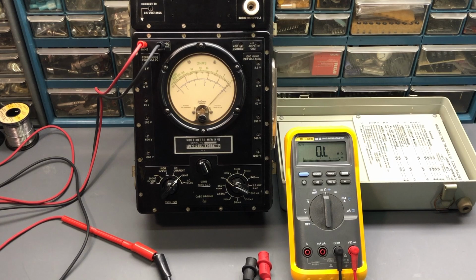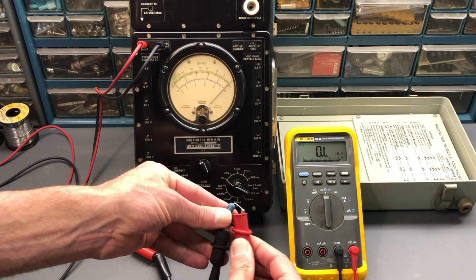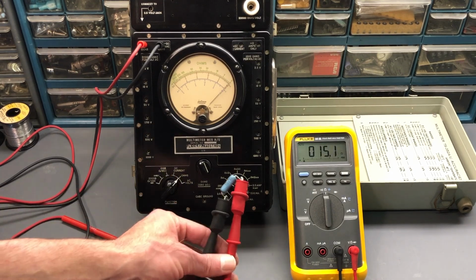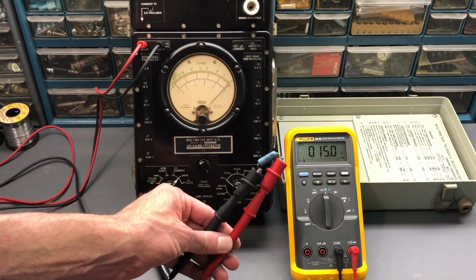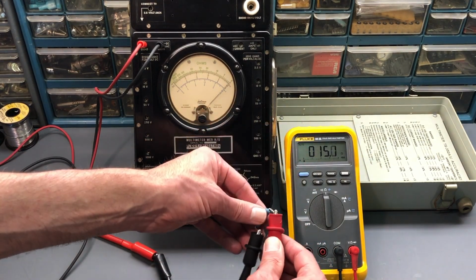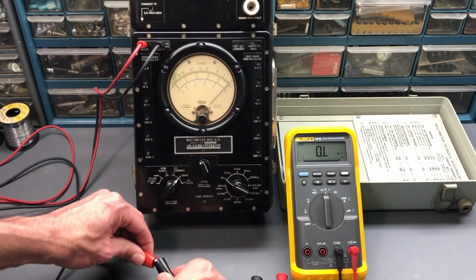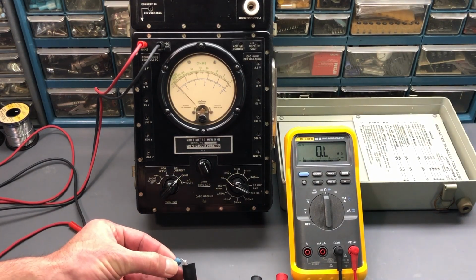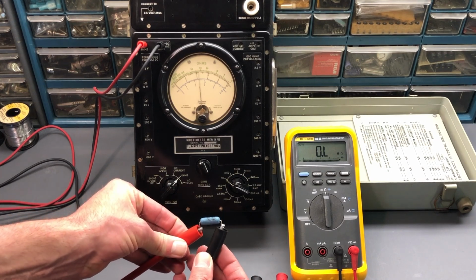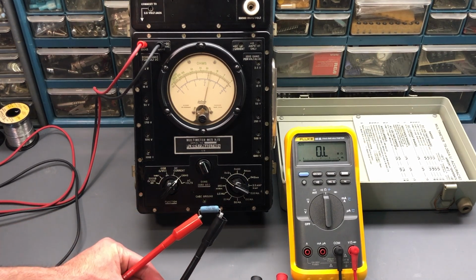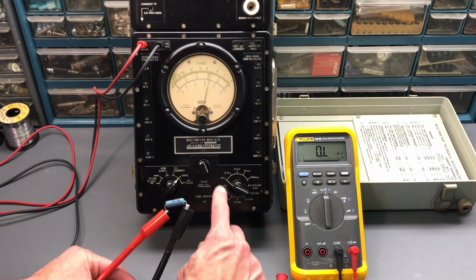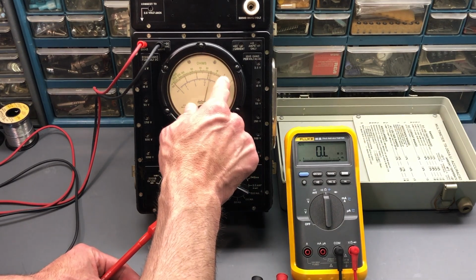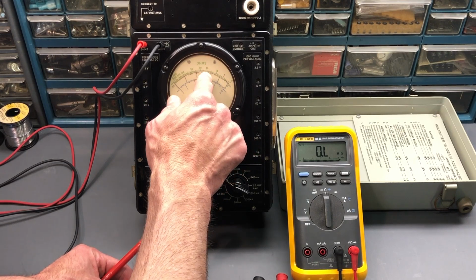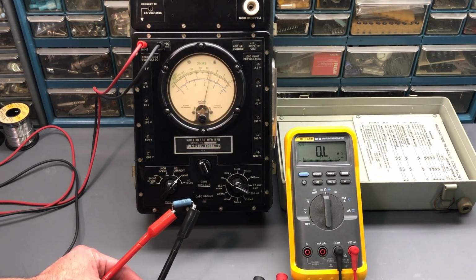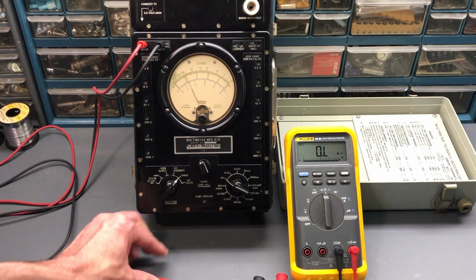So the first resistor is a 15 ohm. That's what it's marked as. So let's see how it actually reads. 15.1. All right, that's looking very good. On the R times 1, we're reading across the top: 0, 5, 10 ohms, 20 ohms. Of course, 15 is right in the middle, and it's exactly where it's indicating. So that looks very good. No problems there.